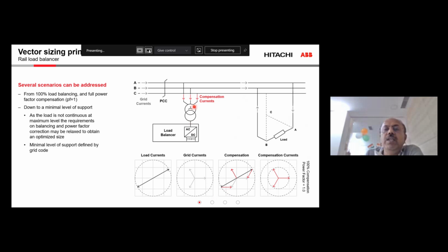So what we see here is that this load balancer is connected to the three phase, whereas the railway network feeding station is connected to the two phases. So one phase is unconnected. The load balancer will draw the current from the unconnected phase and then try to feed or compensate for the connected phases. So in that sense, not only the reactive power, it will also compensate for the real power unbalance.